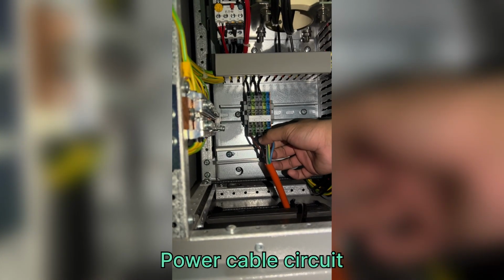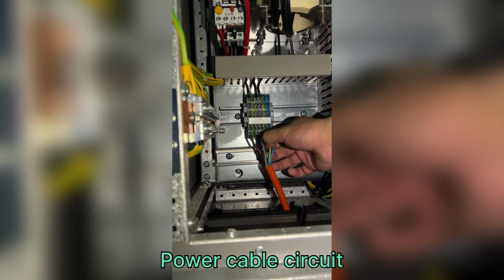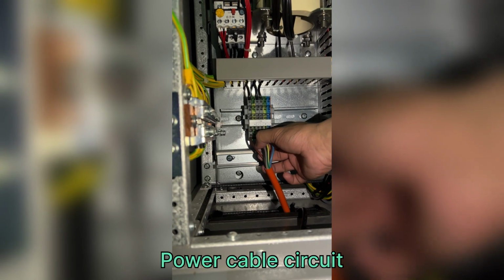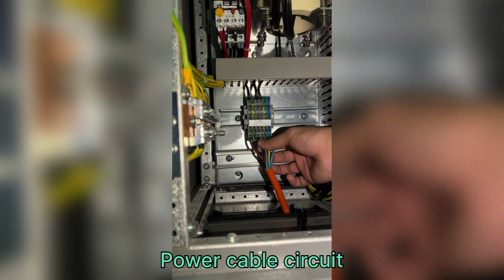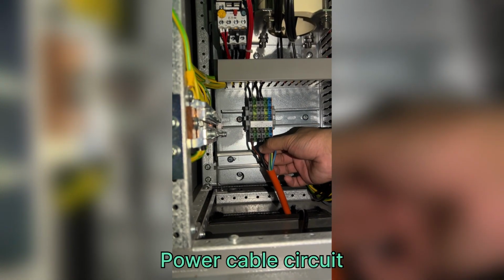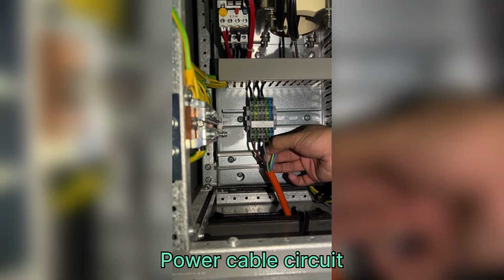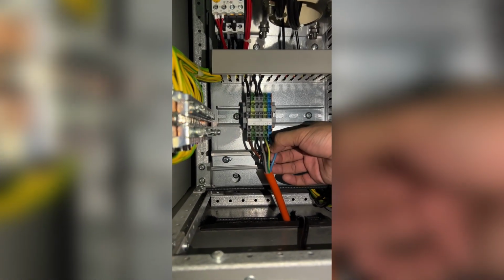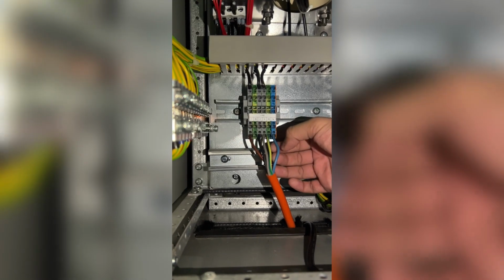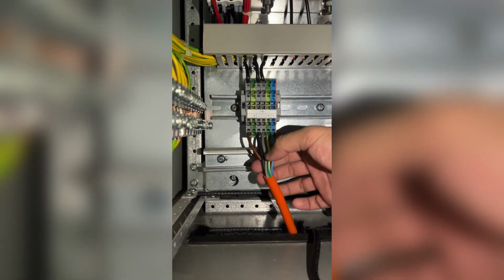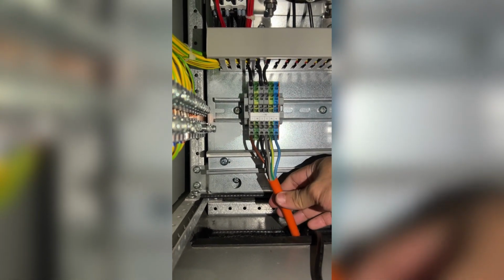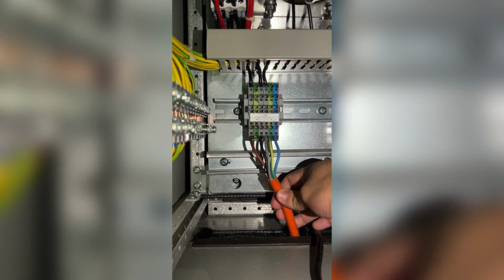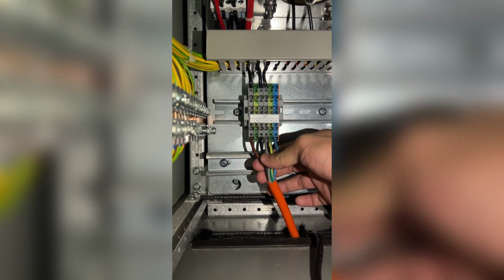The first one is trace power cable circuit. The three phase has to be connected to 1, 2 and 3. The PE is for the ground of the input cable. If the input cable provides a neutral ground, then this can be connected to neutral, but it is not needed. For input protection, there are varistors between the three phases and the PE.